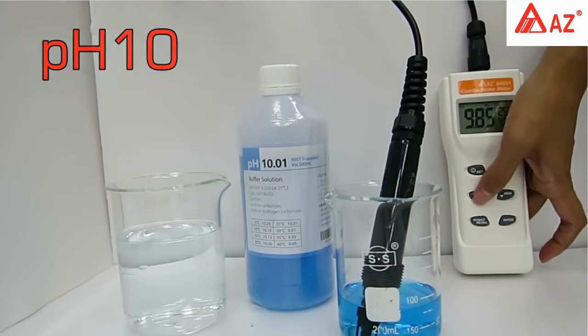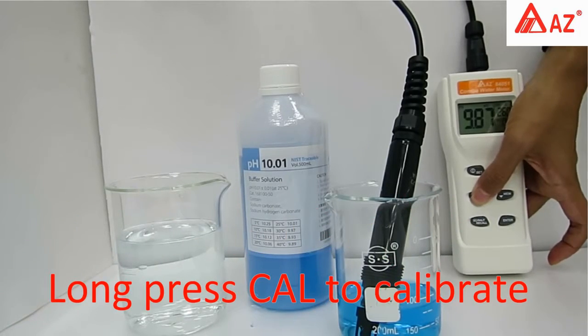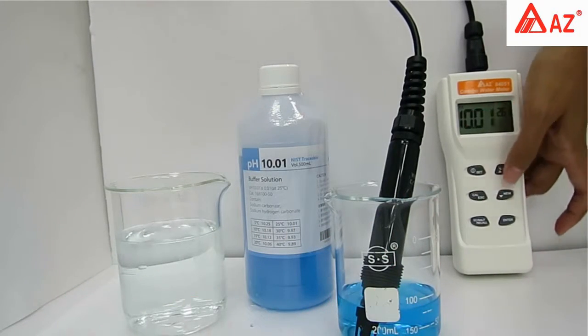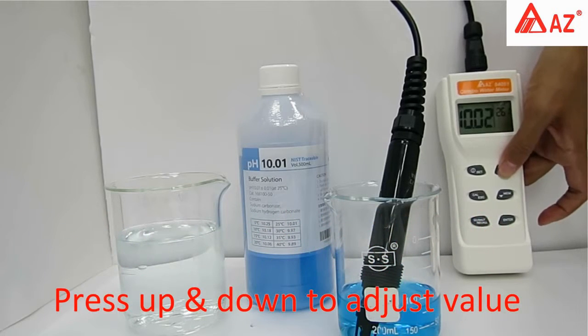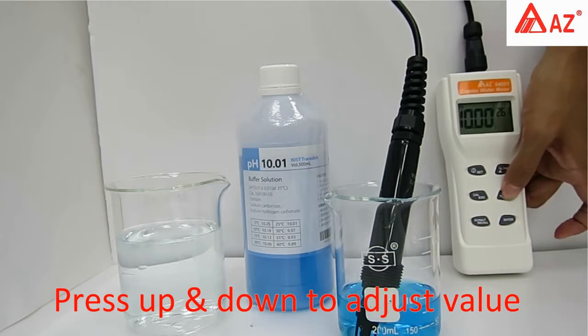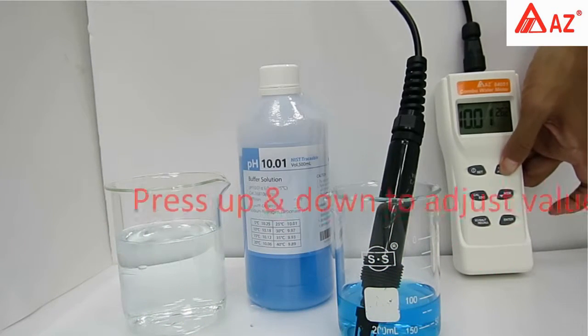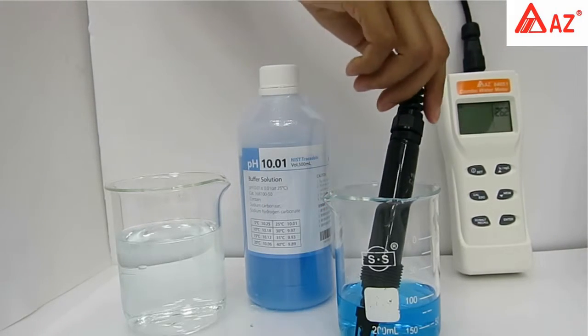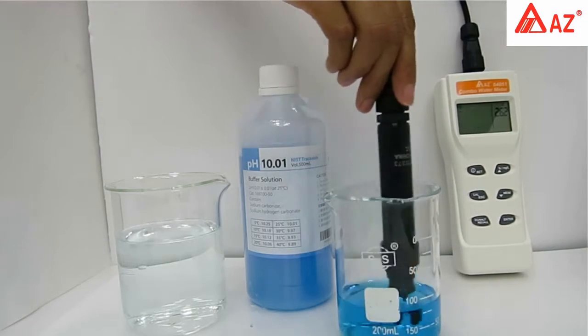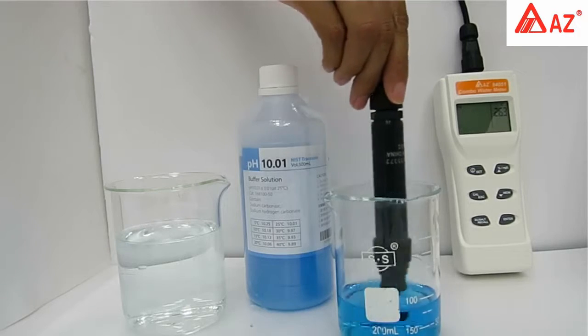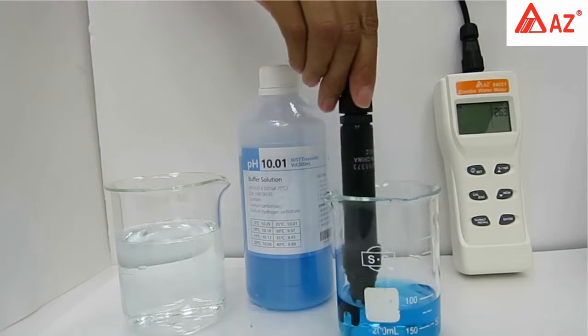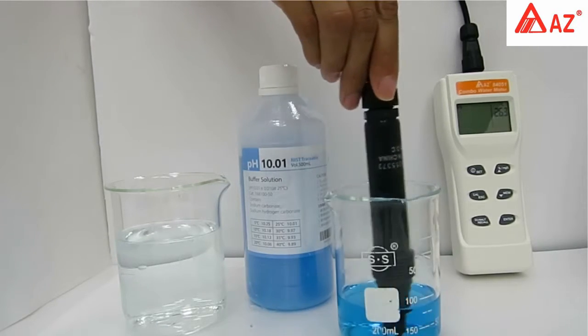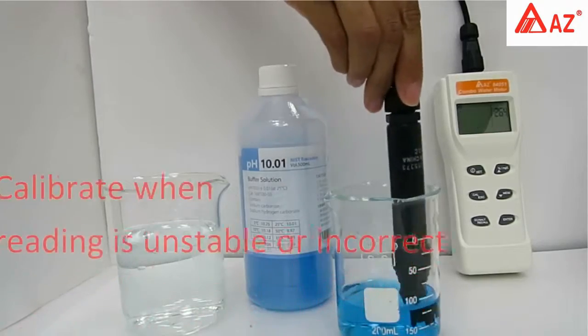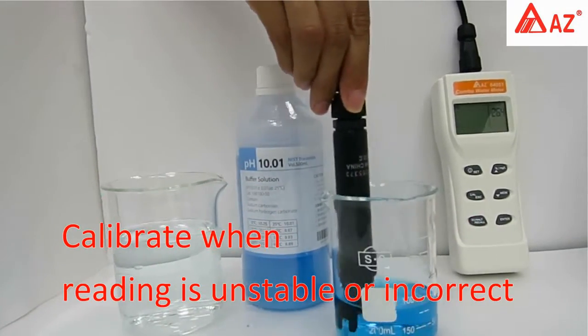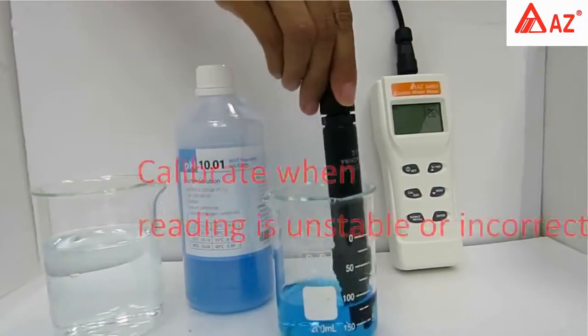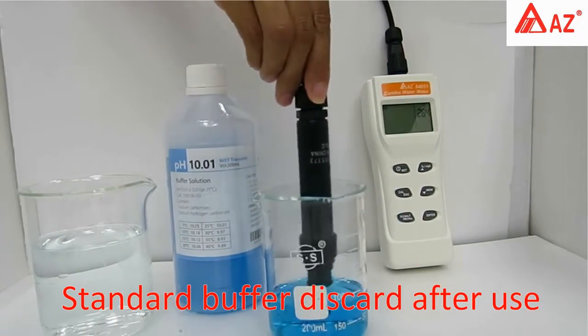pH 10. Long press cal to enter calibration. Set the standard value using the up and down keys. Use a transparent container and make sure the pH electrode is completely immersed in buffer. Stir gently to get a homogeneous condition. Calibrate when the pH reading is unstable or incorrect. Do not reuse standard buffer.